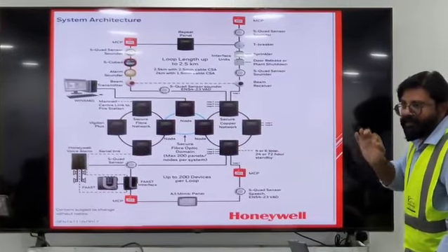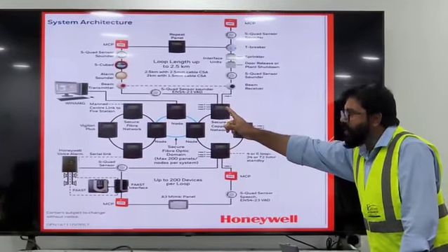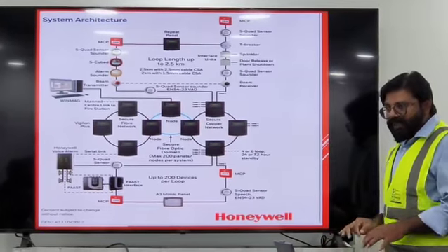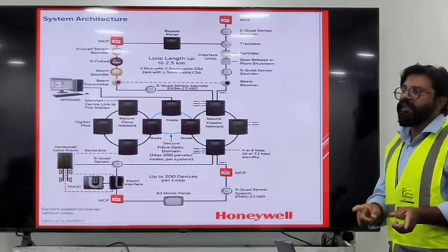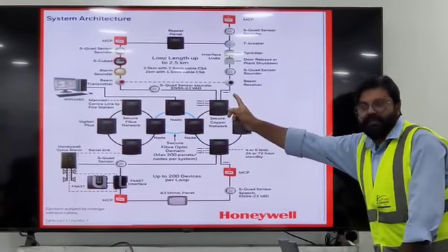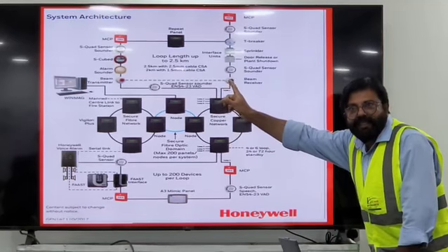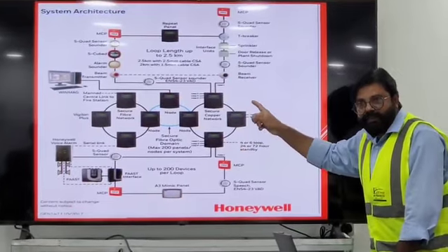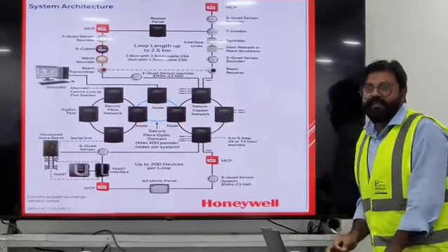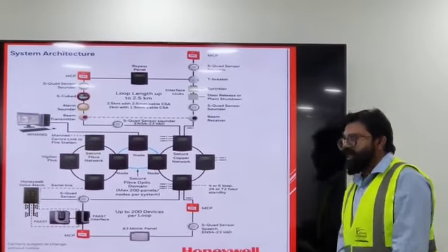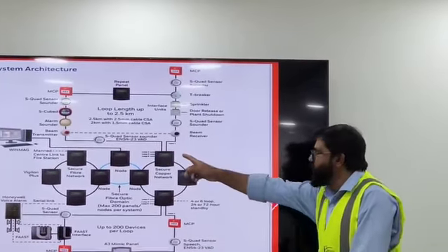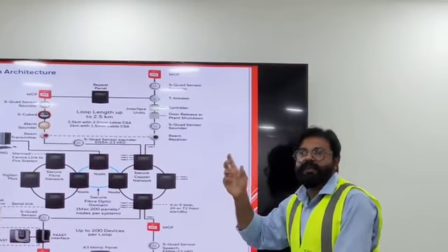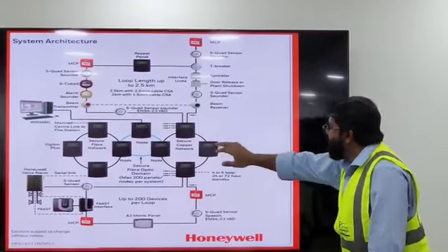Again, I am telling you, for this panel itself, loop 1, loop 2, loop 3, loop 4. For our labelings, as per the matrix and drawing, this is loop number 5, 6, 7, 8, and for itself, it's 1, 2, 3, 4. So 1 to 8. It means if the panel gives you the indication of a fire at panel number 2, loop number 1, where is the fire actually? Number 5, loop number 5. You are understanding. Okay, this is the network.